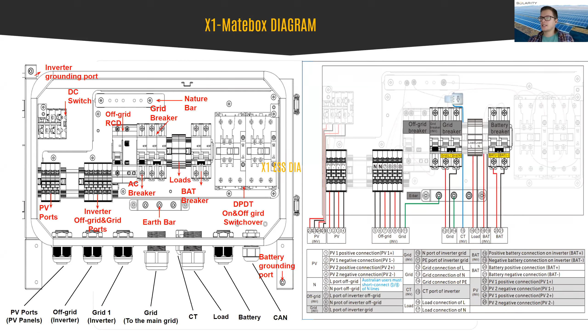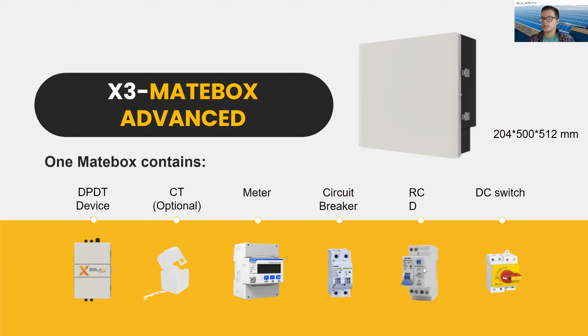And there's also the Matebox for three-phase installation. In this case, a meter is required, because the current transformer and in general the meter is the eyes and the ears of your energy storage system. It measures how much energy the system supplies back to the grid. For the single phase solution, the current transformer is enough because it measures just the current. So for the three-phase solution, you need to measure also the voltage, and the energy meter measures the voltage. And it also includes circuit breakers, RCDs, and the DC switch.